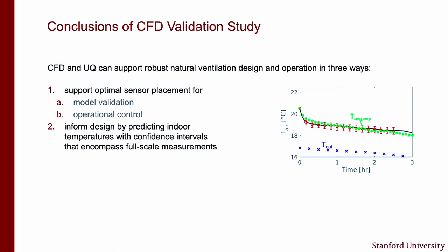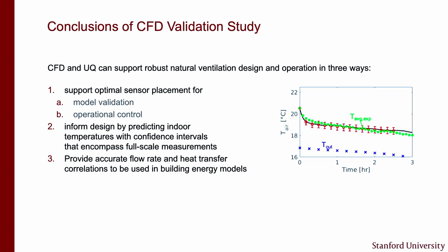Second, we can inform design by predicting the indoor temperatures you will see in your buildings with quantified confidence intervals, and we've shown these really encompass full-scale measurements. And third, from the CFD we can get very accurate flow rate and heat transfer correlations that can go into building energy models like EnergyPlus, making those predictions much more accurate.